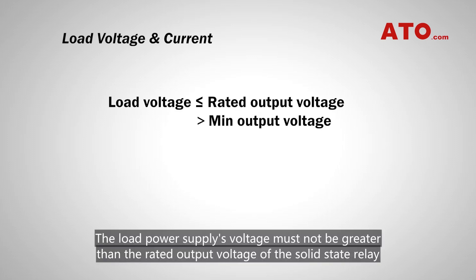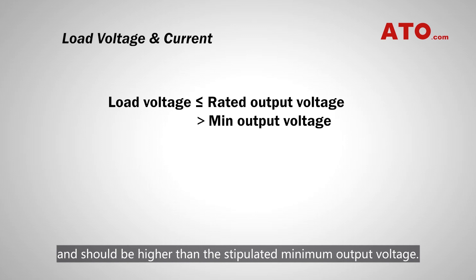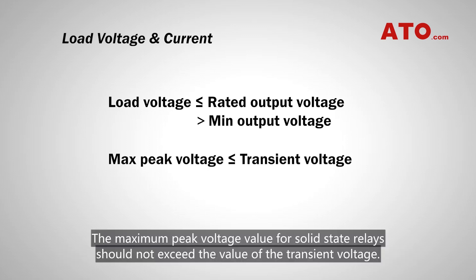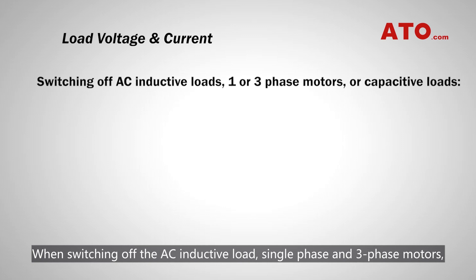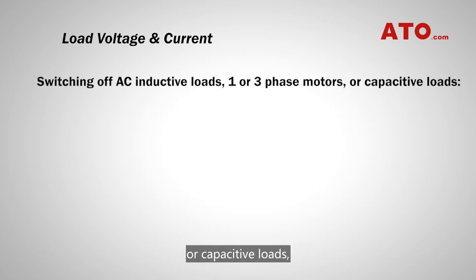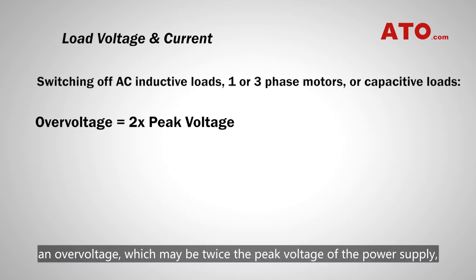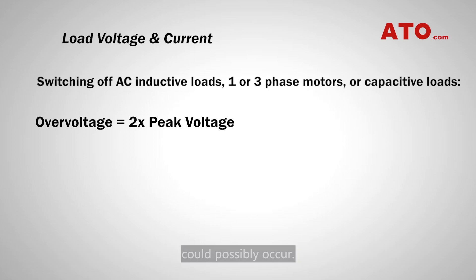Number 2: Determine the load voltage and current. The load power supply's voltage must not be greater than the rated output voltage of the solid-state relay, and should be higher than the stipulated minimum output voltage. The maximum peak voltage value for solid-state relays should not exceed the value of the transient voltage. When switching off the AC inductive load, single-phase and three-phase motors, or capacitive loads, an overvoltage which may be twice the peak voltage of the power supply could possibly occur.